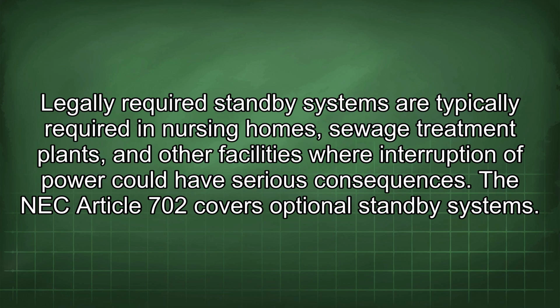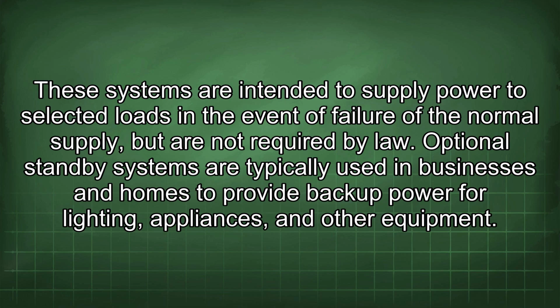NEC Article 702 covers optional standby systems. These systems are intended to supply power to selected loads in the event of failure of the normal supply, but are not required by law. Optional standby systems are typically used in businesses and homes to provide backup power for lighting, appliances, and other equipment.